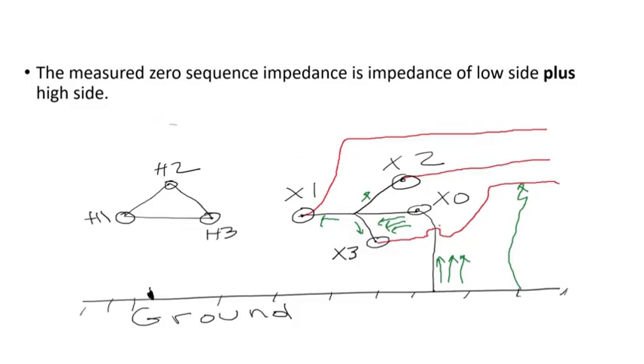As a quick reminder: if you have a delta and a Y, and the ground is on the Y side, the delta has no ground and no neutral — so there is no physical connection to ground on the delta side. If power lines going through a substation have a phase faulted to ground — say a tree falls and creates a path to ground — current will flow through the neutral. Three units flow through the neutral, with one unit per phase. Since there is no connection through ground to the delta, the delta will not be impacted.